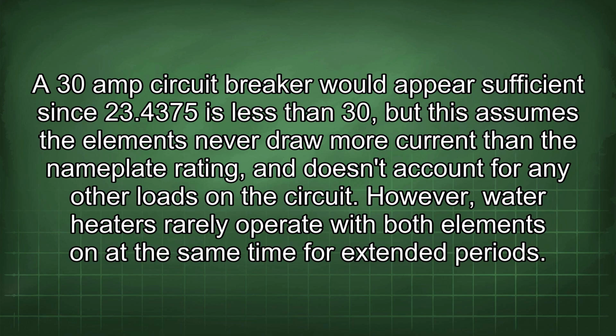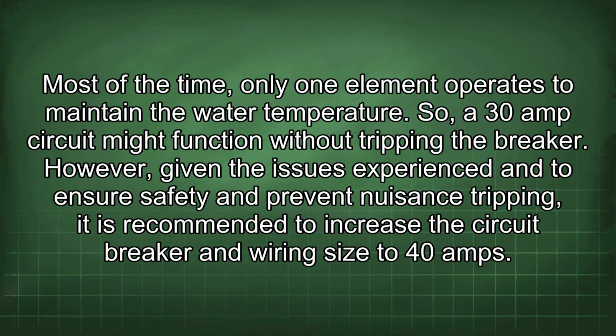A 30 amp circuit breaker would appear sufficient since 23.4375 is less than 30, but this assumes the elements never draw more current than the nameplate rating and doesn't account for any other loads on the circuit. However, water heaters rarely operate with both elements on at the same time for extended periods. Most of the time, only one element operates to maintain the water temperature. So, a 30 amp circuit might function without tripping the breaker.